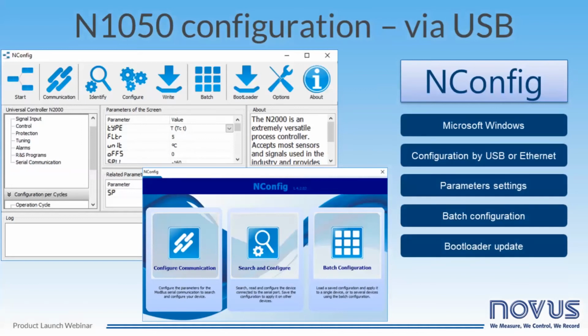Regarding configuration, as mentioned before, N1050 configuration is made with the NConfig software. This is the software. Maybe most of you already know it. It allows to configure all parameters, but not only that. N1050 can be set directly by USB or by Ethernet connection through Modbus TCP to Modbus RTU gateway. N1050 also allows batch configuration and firmware or bootloader update. Okay, so it's a good tool for maintenance of the equipment.